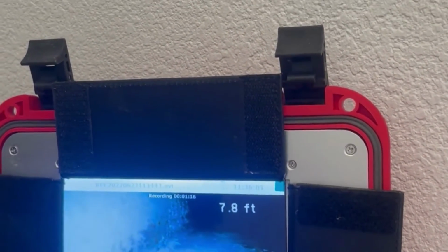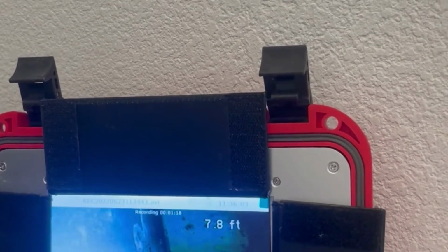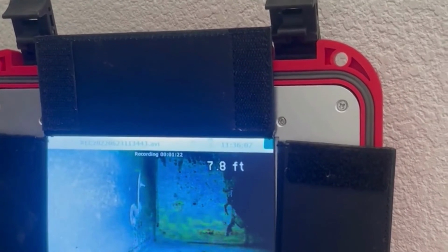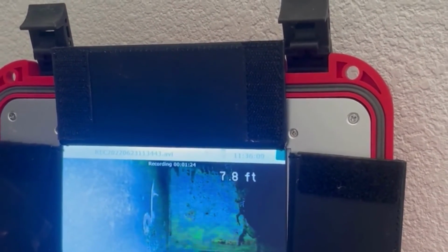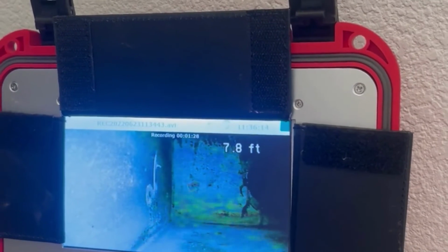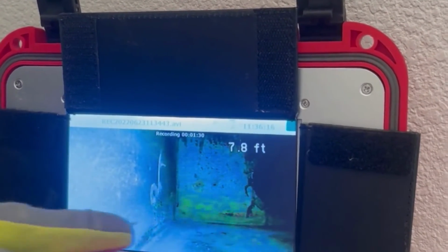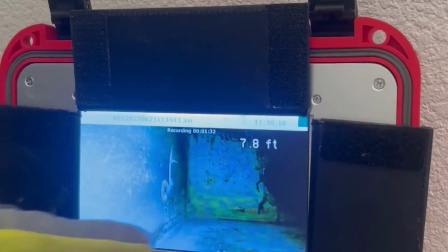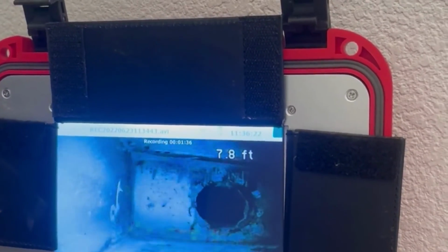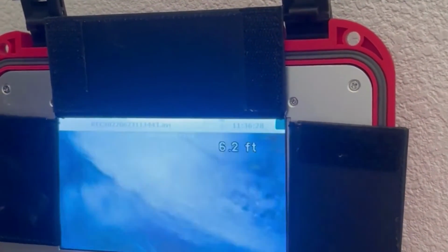So we're into it now. You know, there's some minor corrosion, which can happen from condensation that occurs, but you don't really see what I'd also see a lot of times, which would be water lines, that the water level has risen in there, and that's when you know you've had a significant amount of moisture, because this is the lowest point of the system. It's actually about 6 inches lower here than the ductwork, so you can get a few inches anyhow. And that looks nice and clean there, so that's a really good sign. That's one thing we want to note.